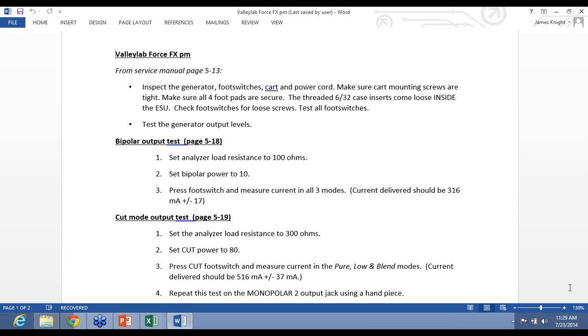So you need to set your analyzer load to 100 ohms, and you set the bipolar power to 1 to 10, and then you test it in all 3 modes.